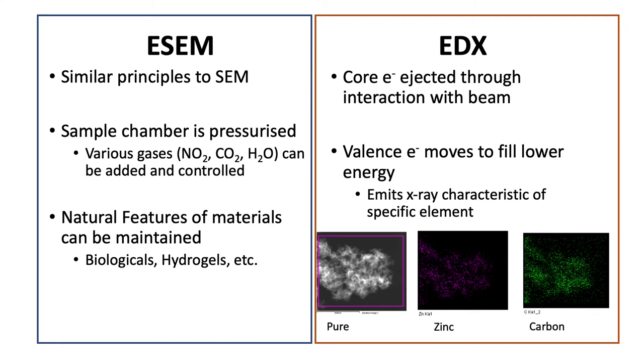Another interesting type of experiment that can be done with an SEM is energy dispersive spectroscopy or EDX or EDS. In this case, you can identify the distribution of elements in a sample. This is done because the accelerating voltage used to emit the electrons is capable of ejecting inner shell electrons from the atoms that they hit. Since all of these electrons come off with very characteristic energies, if a detector is properly equipped, it can detect from which point in space an electron belonging to a certain parent atom was sent. This technique is often used in material science to study the dispersity of certain defects that might have been put there on purpose.